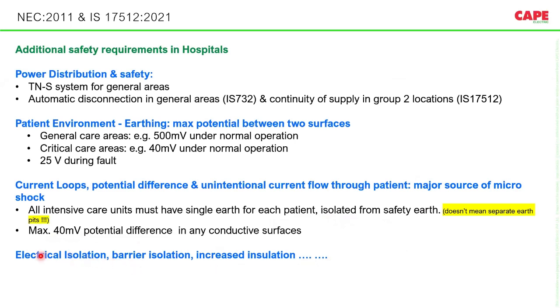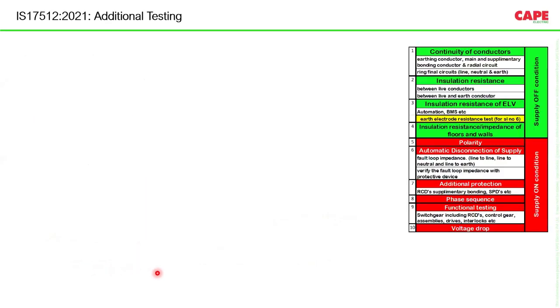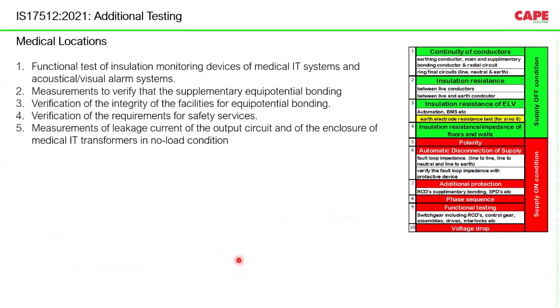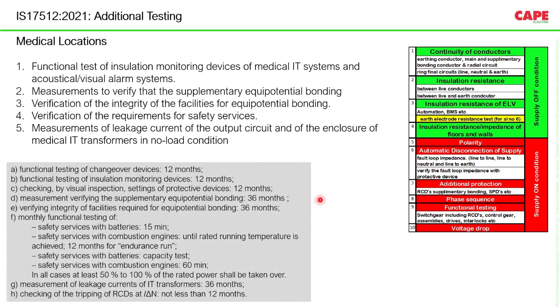So then you can also go for safety measures such as electrical isolation with an isolation transformer, barriers, then increased safety measures are also required. Similarly, the NEC is recommending additional testing for hospital medical environment. There are 5 tests. The first one is the insulation monitoring device should be tested.